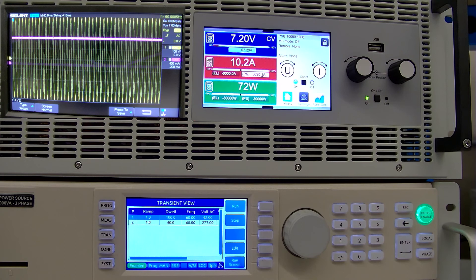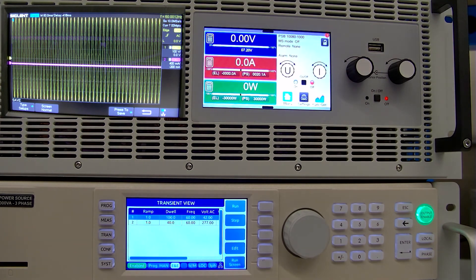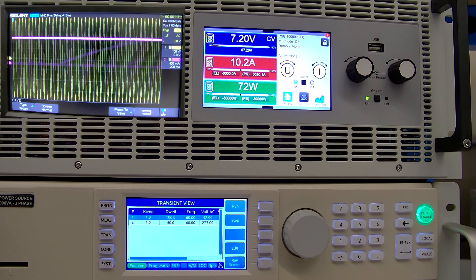We're all set up again. Hopefully this time it works. We're going to see a power fault on the PSB, and then it will come back up as soon as the voltage comes back. And then we can re-enable the output. There — you saw the output go to zero. When the voltage sagged for too long, our unit no longer has the power fault — that's gone away, but our output is off. We just go back and re-enable the output, and we're good to go. It is nice that the unit recovers itself automatically, as long as that voltage is not gone long enough for the unit to power off completely.